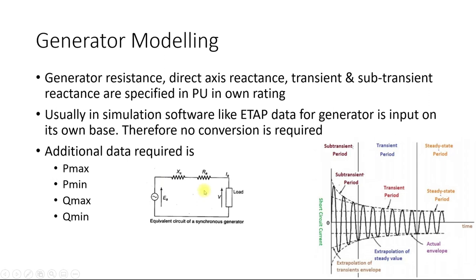For a generator, these reactance values vary with respect to time. Whenever there is a short circuit fault on the generator side or on the system, your generator goes through some transformation. Usually for the first few cycles, your reactance is limited by the sub-transient period, and the reactance within this period is known as sub-transient reactance.